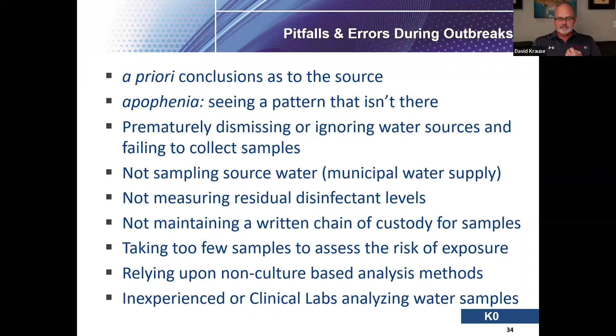One of the things you need to do is take water and swab samples, and when you do, make sure you submit them to a laboratory for culture analysis. The laboratories must analyze samples by culture methods — one of those methods is ISO 11731 — and you need to make sure they do analyze by that. The problem is that some labs will culture but you might not get the detection limit you're really looking for, and sometimes they don't even let you know what it is.